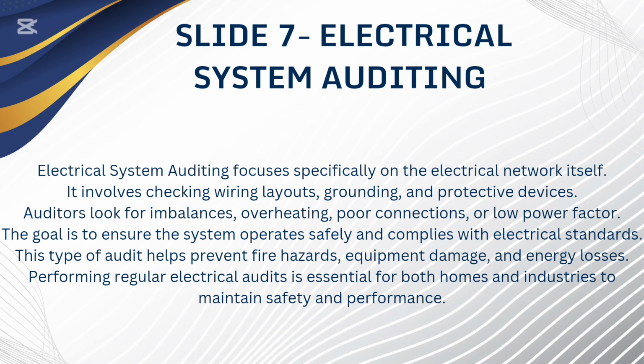Electrical system auditing. Electrical system auditing focuses specifically on the electrical network itself. It involves checking wiring layouts, grounding, and protective devices. Auditors look for imbalances, overheating, poor connections, or low power factor. The goal is to ensure the system operates safely and complies with electrical standards. This type of audit helps prevent fire hazards, equipment damage, and energy losses.